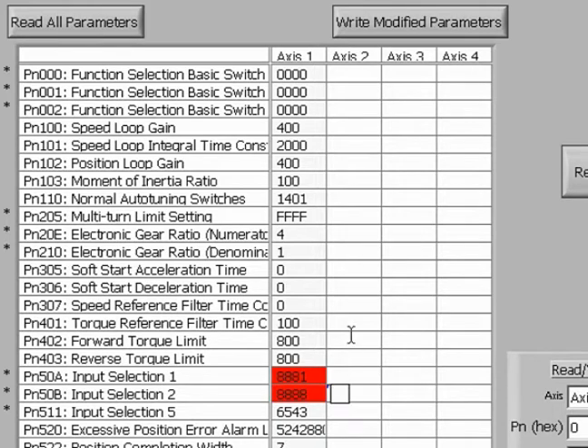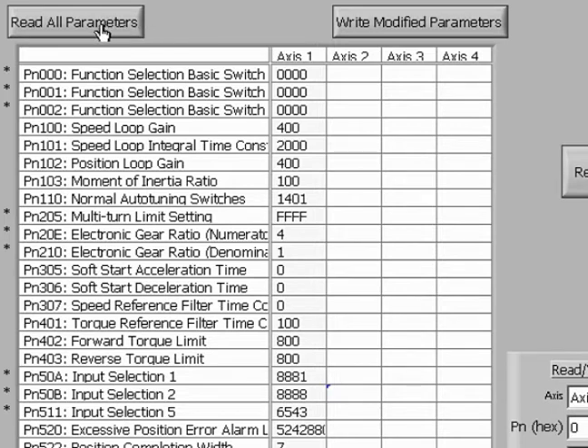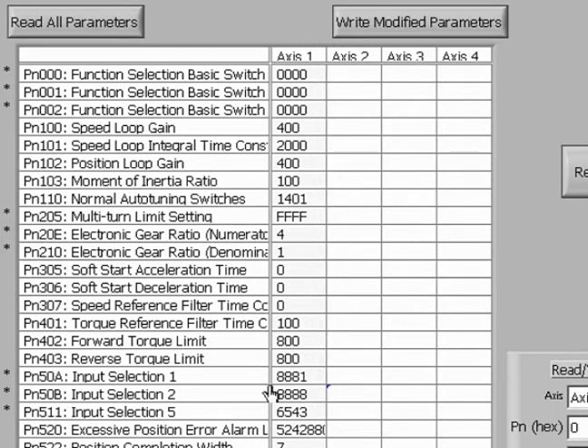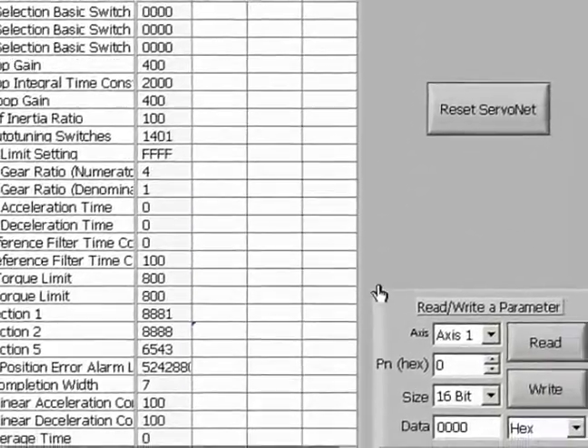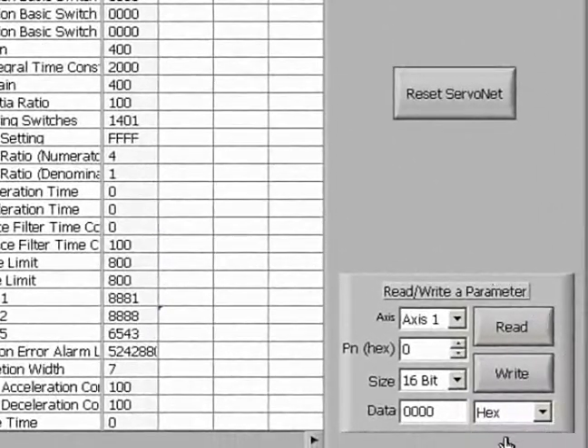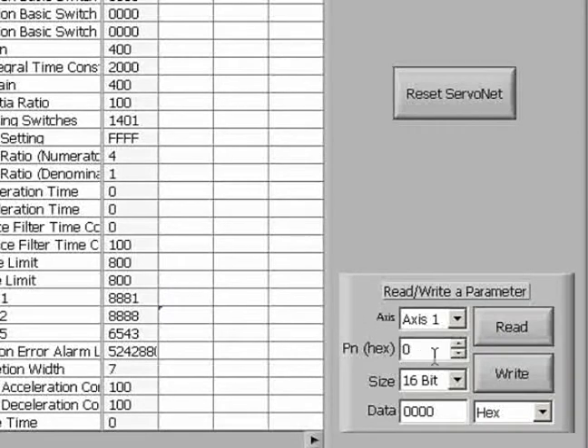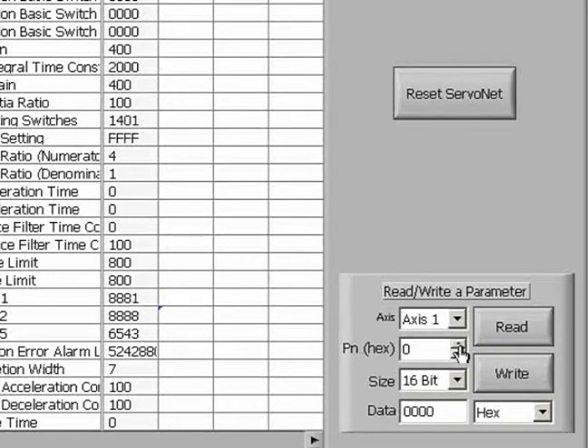Now, we can write the modified parameters to the drive. When we go back and click Read, we see that the changes have been saved to the drive. Another way we could have made these changes is by calling up each parameter by its data tag in this area, but we chose instead to make changes in the drive's data field section.